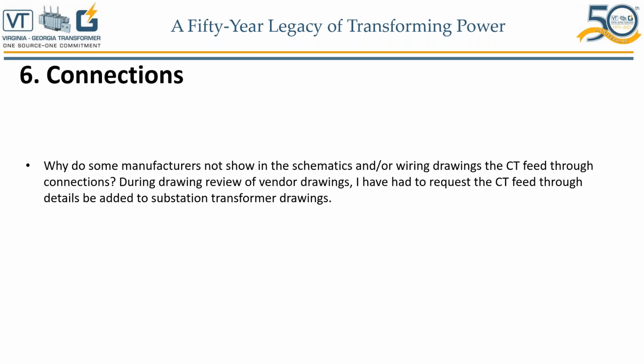Nonetheless, the output of the CTs first. If they were inside the tank, bushing mounted CTs as an example, let's take a simple example here. The CTs are mounted inside the tank and the bushing goes through these CTs. The output of the CT cables, now running inside the tank, comes to a feed through, and from this feed through we take the output of the CTs and run it through a conduit down to the control cabinet.